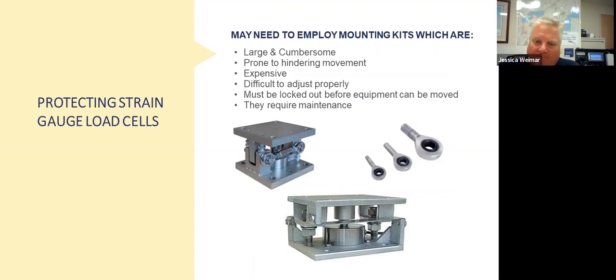You'll note here, we just talked about the fact that the units themselves don't like to be overloaded. They don't like to be twisted. They don't like to be subject to side loads. Any kind of a shock load is difficult for a strain gauge. So what do we do about that? If you're going to employ a strain gauge load cell, you've got to put some ancillary equipment around the strain gauge in order to protect it from being subject to that load.